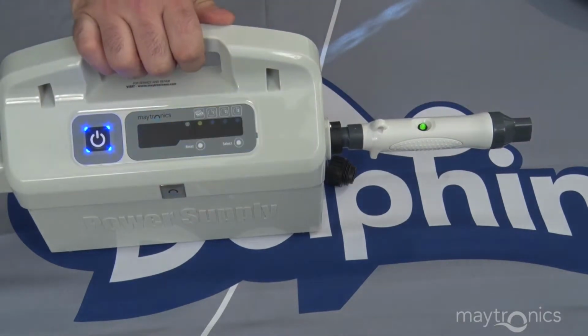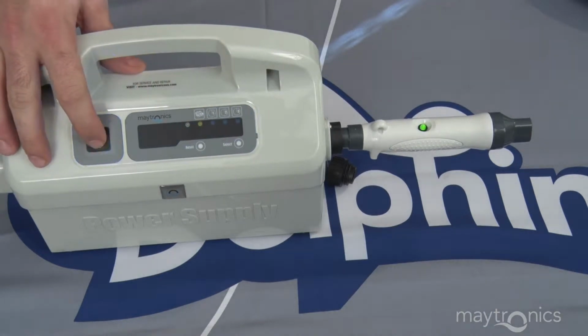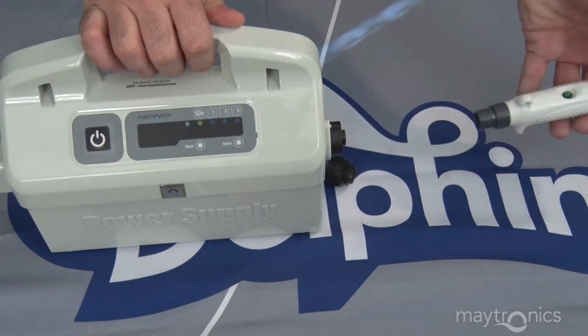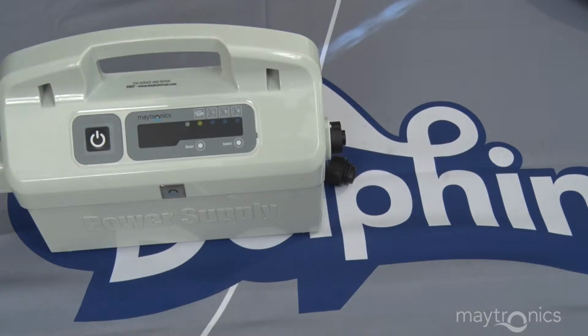If the green LED indicator light on the tester lights up, it means the power supply is functioning properly. If the green LED does not light up, the power supply will have to be replaced. After replacing the power supply, try the self-test cycle again to make sure that the unit is now functioning properly.